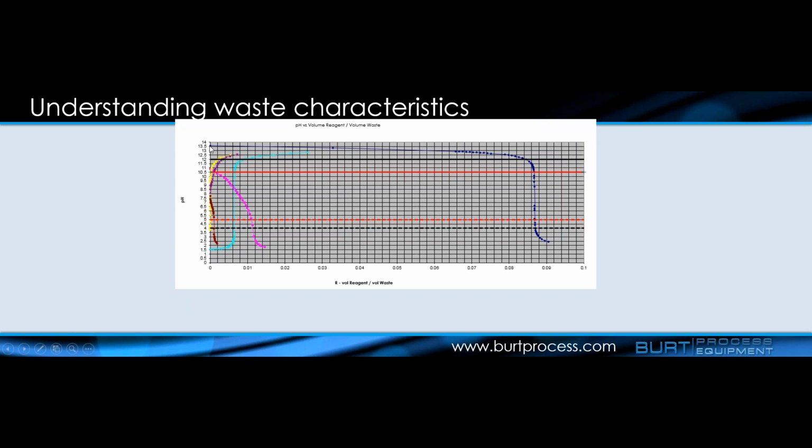a very strong 13.5. This is actually potassium hydroxide. Down here, we have a 1.5 acid stream coming into our system, and then these sort of straight lines here, not a lot of reagent injection. These are waste constituents that start low, 2.5, 4. This one up here, 11.